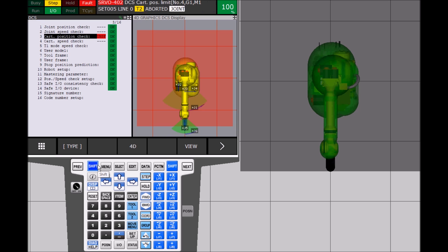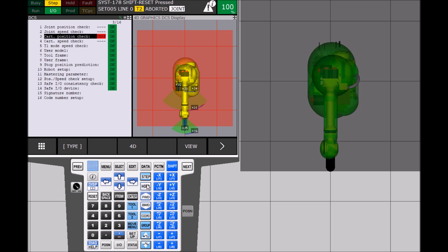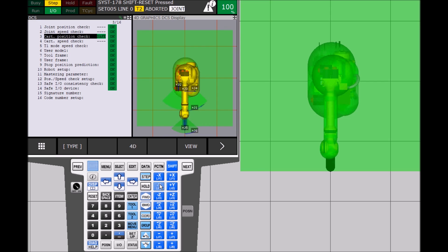Select shift and reset. In this example, we are in world jog mode and the robot has gone out of zone in the plus or minus y direction. So to get back into the zone, we will jog using the plus or minus y jog keys.